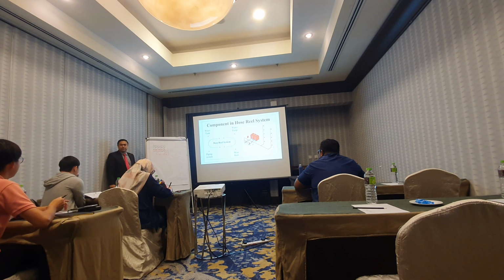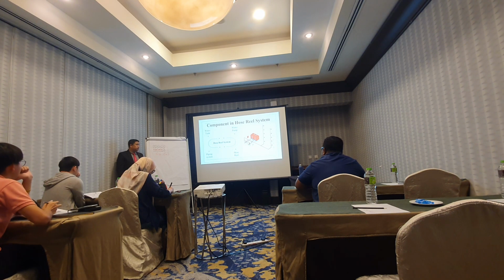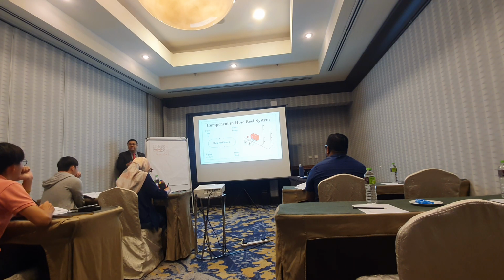Normally, we do a separation when we have a system like sprinkler and wet riser. Because when you do a maintenance for a bigger tank like that, for a hose reel it's just a very small one. So you know when you service a hose reel, you can have a backup system, which is your backup is extinguisher, no problem. Or you can plan for it so that you can service the hose reel system whenever there are nobody inside the building, no problem.